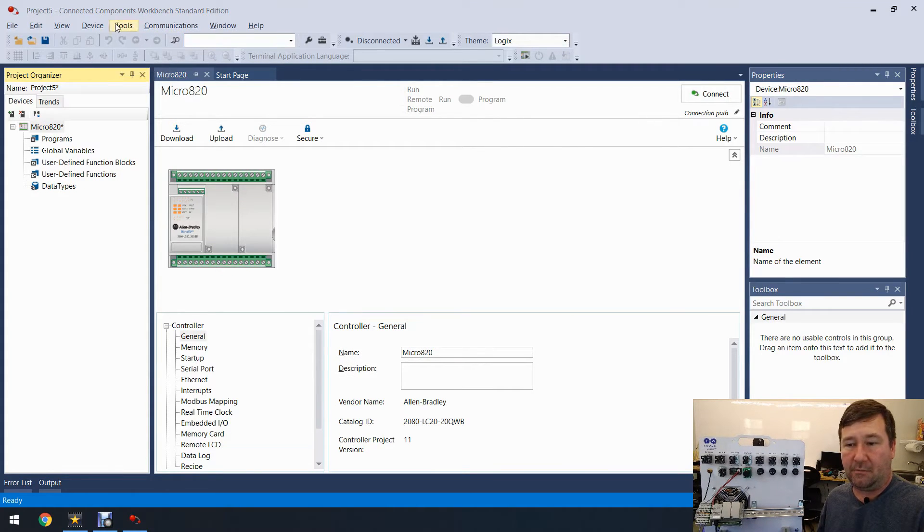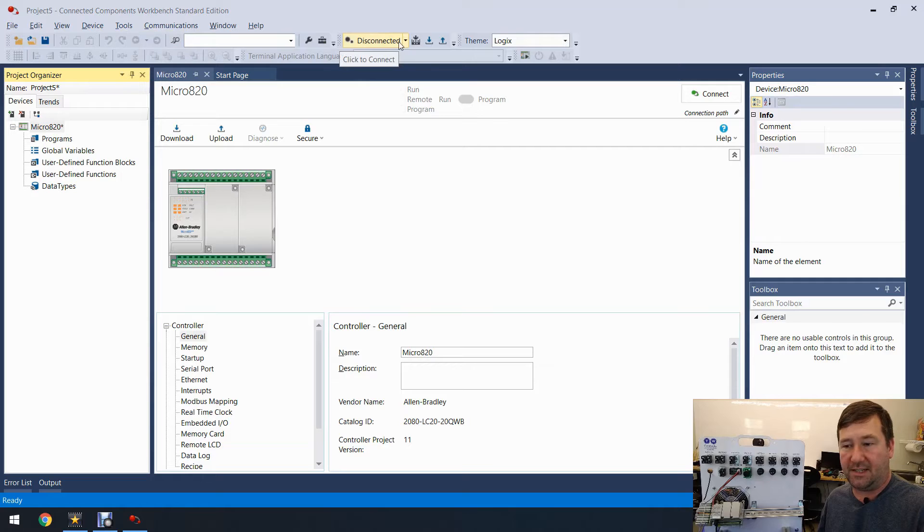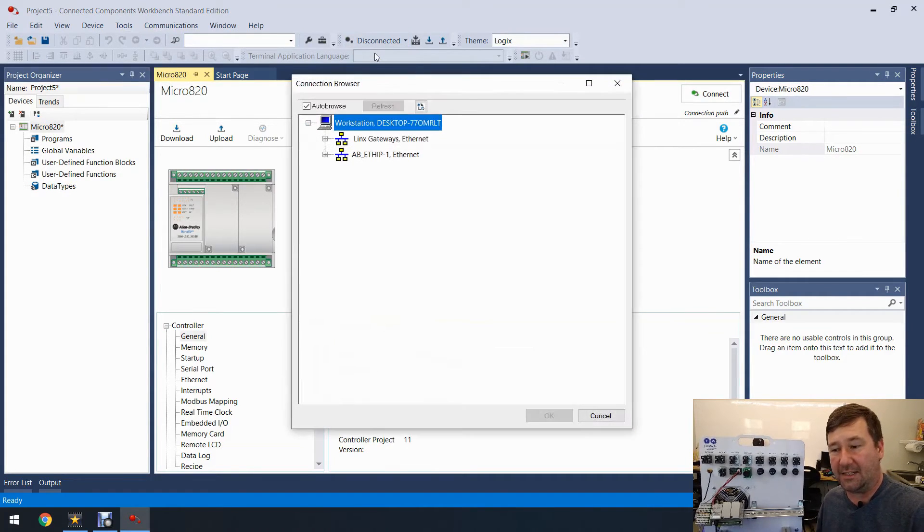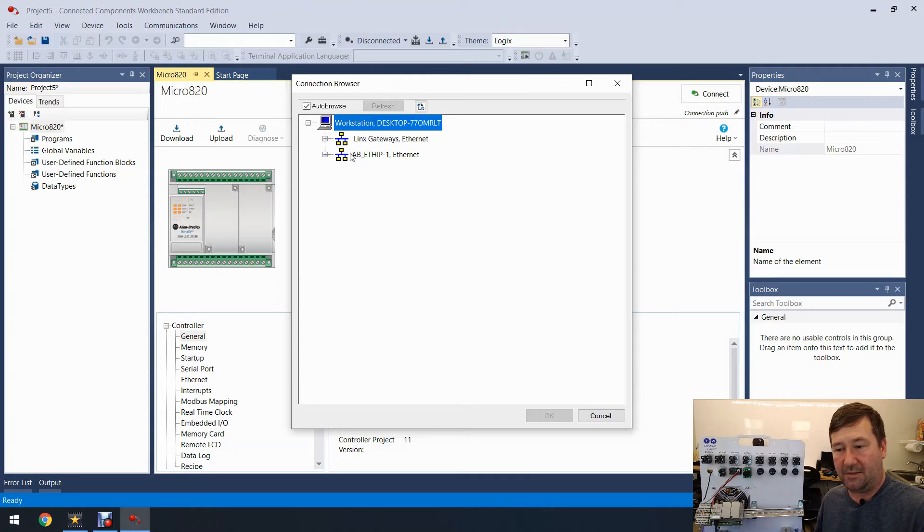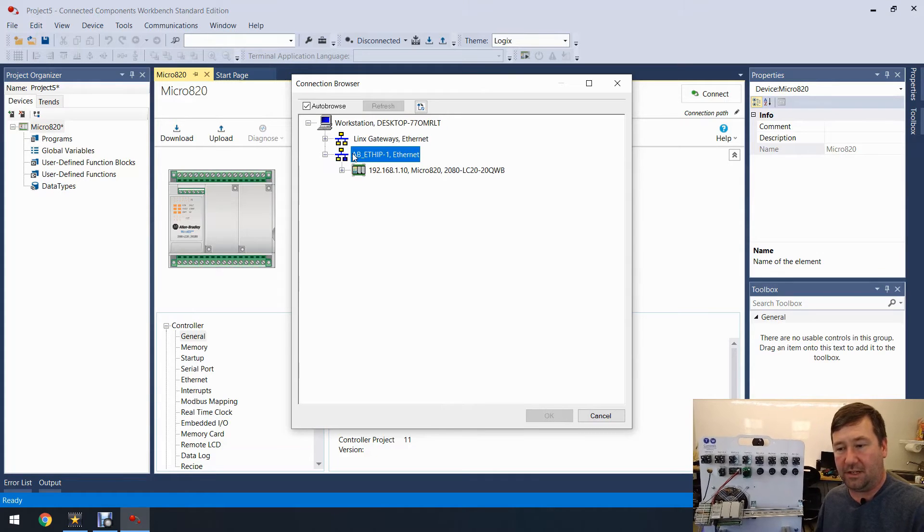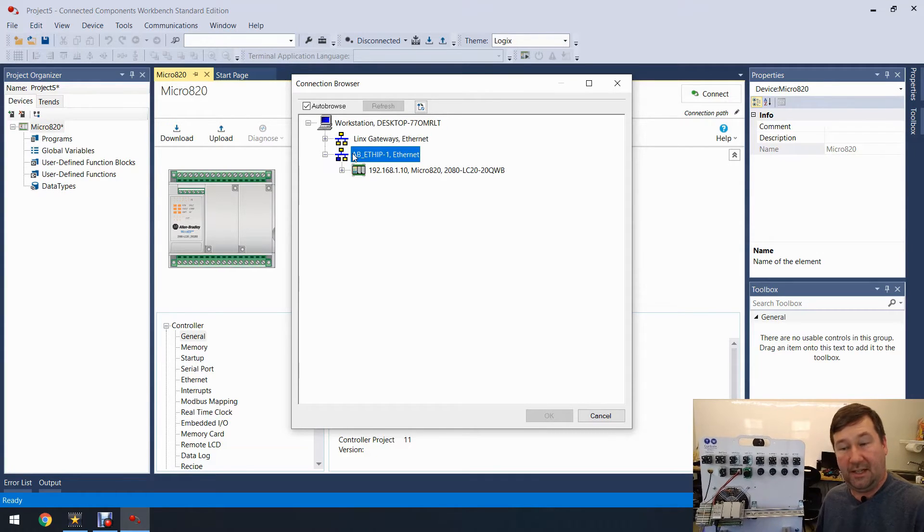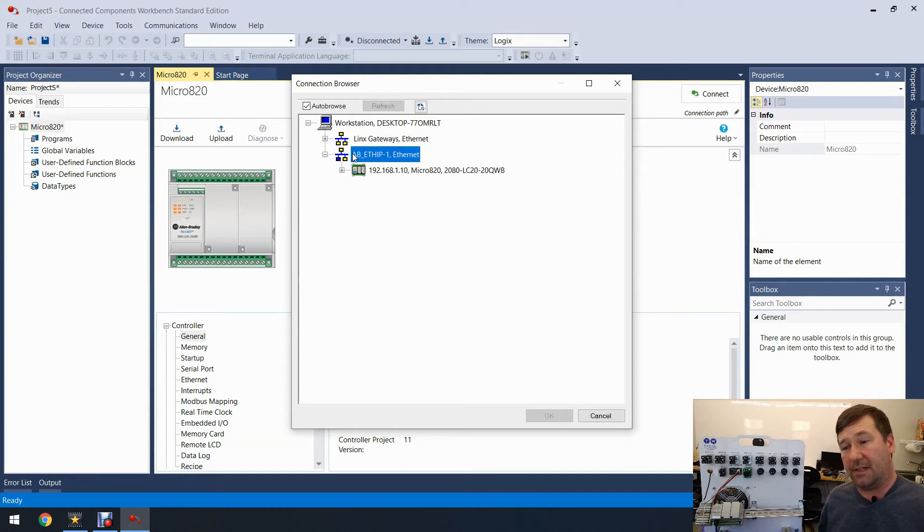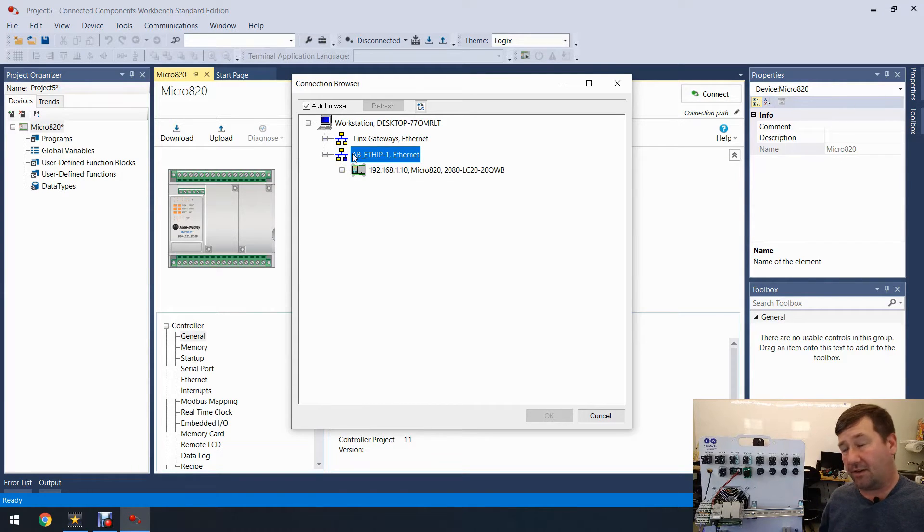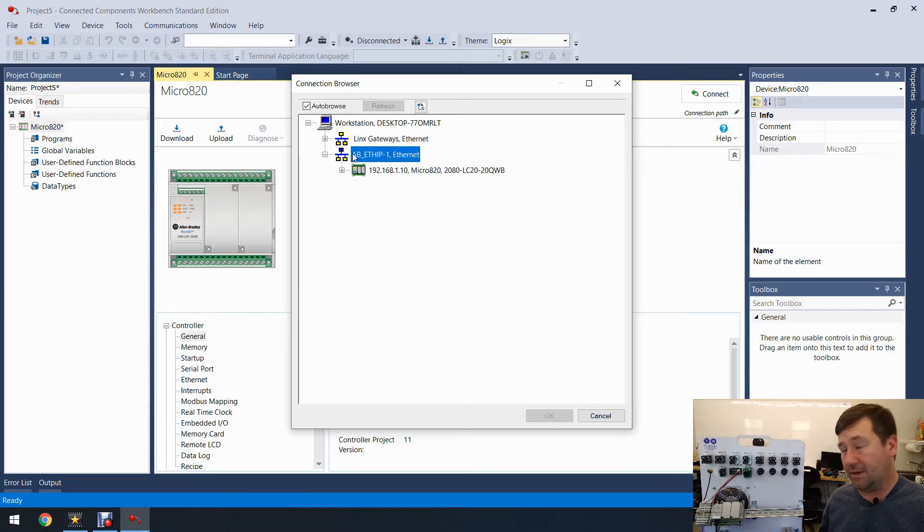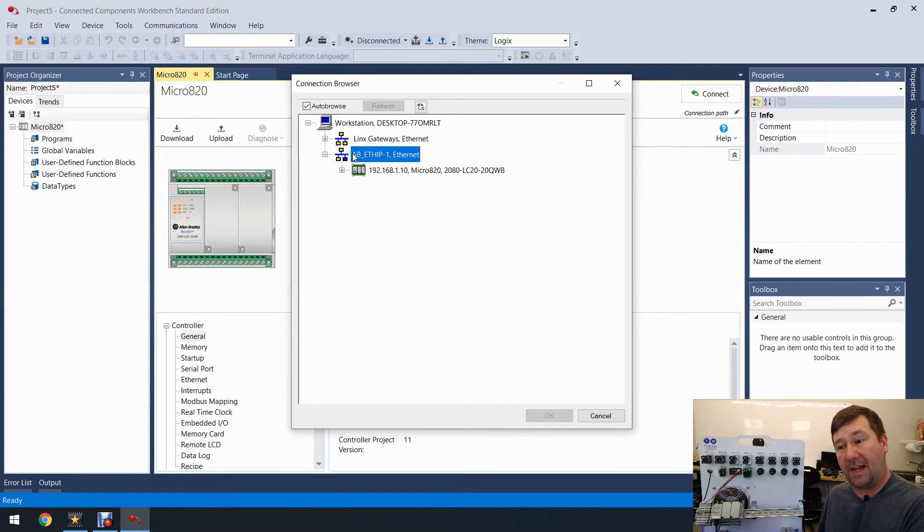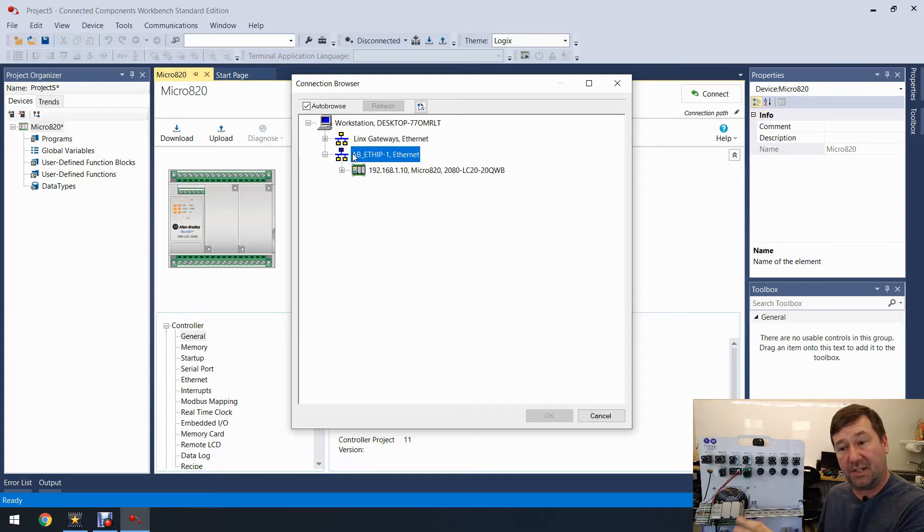And then we're going to go right here where it says Disconnected, we're going to click the arrow right beside of it and click Connect. And now we have that Ethernet/IP driver so we're going to click on it and there's our PLC. Now what if it didn't show up? If it didn't, then chances are either your IP address is not configured right or something is blocking those Ethernet/IP driver packets that normally would discover this.